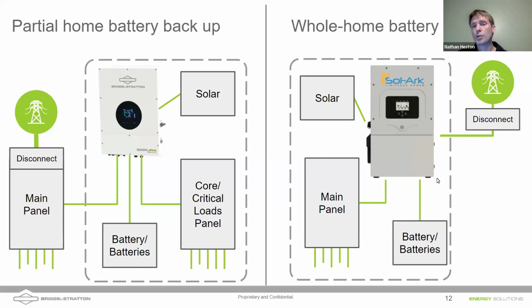There's no separation for loads in the home. This means, of course, you could tax the inverter more than it's capable of, because by battery alone, the Sol-Ark 15k is only capable of 12 kilowatts of continuous output. But if you overload the inverter and turn the device off that is causing the overload, the inverter will reset itself and be able to back up the entire home. So yes, it is limited backup. It's not as big as a 200 amp service, which is 48 kilowatts. This is only able to do 12 kilowatts on battery only.